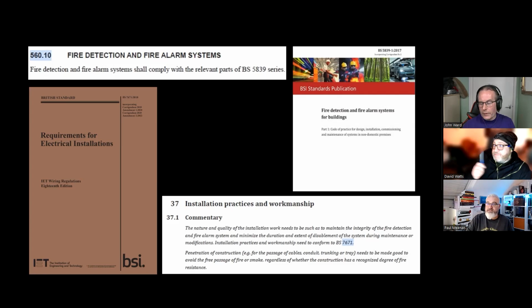Absolutely. Yep. So before we move on from here, the very first question that came in this evening from David was in this area, so I wanted to hold on to it until now. His question was, would not having SPDs on emergency lighting circuits result in a C2 on an EICR? So an emergency lighting circuit, BS 5266 coverage, no SPDs, fixed wiring. Yes. So we've got a crossover here. The same thing can apply to domestics with smoke alarms. Because it's the same thing. It's a safety device, and if there's no surge protection, it could be destroyed, and you wouldn't necessarily know.